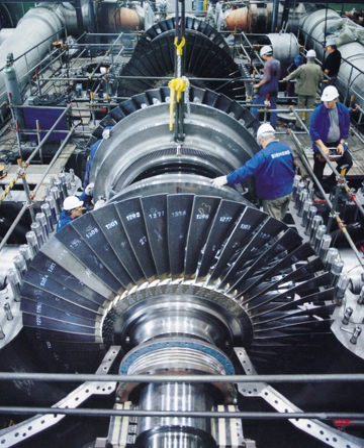If the load on the system increases, the generators will require more torque to spin at that speed and, in a typical power station, more steam must be supplied to the turbines driving them. Thus the steam used and the fuel expended are directly dependent on the quantity of electrical energy supplied. An exception exists for generators incorporating power electronics, such as gearless wind turbines, or linked to a grid through an asynchronous tie such as a HVDC link. These can operate at frequencies independent of the power system frequency.